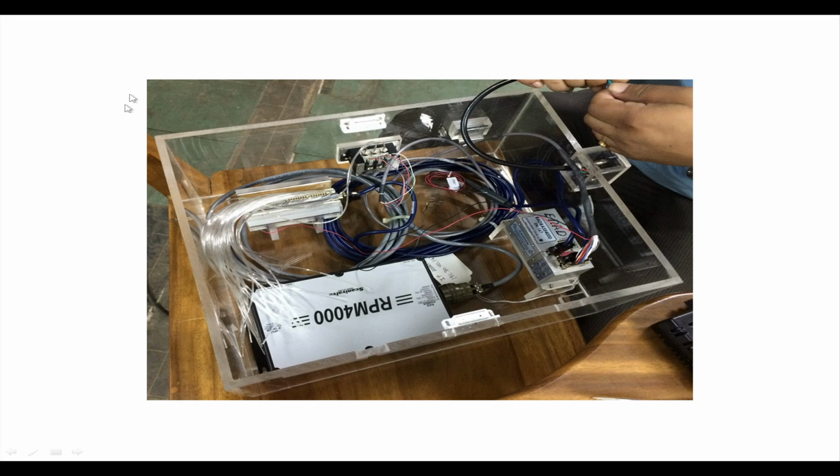No. This assembly we have done. They would not provide it to you. When they provide you, they will give you the bits and pieces. There may be even small units missing here and there. So you have to figure out and then configure it properly. This is done because there are a lot of small gadgets here and there, very expensive and susceptible to damage. If you put them together in a nice compact system, it is much easier to work with. It is a matter of convenience and ease of maintenance, and other advantages, that we figured out a system like this and put them together.